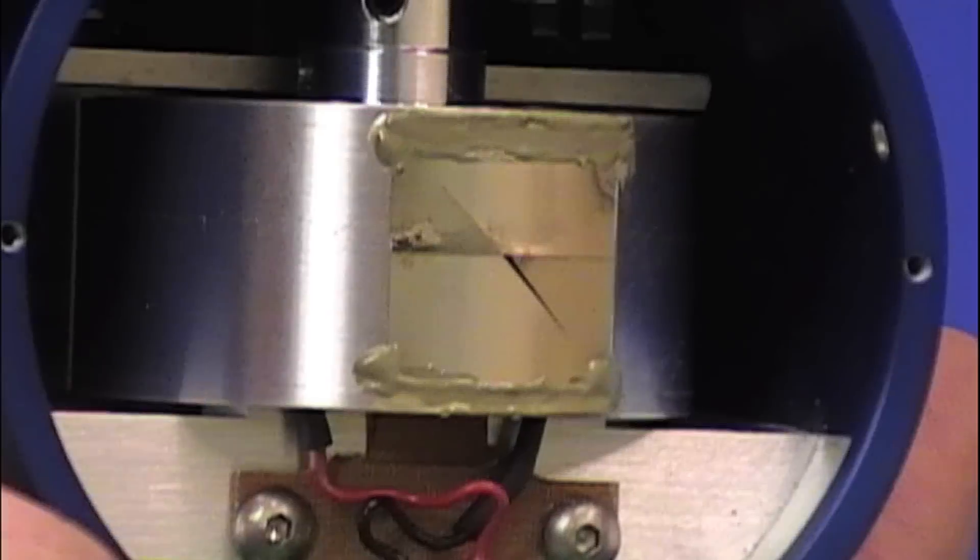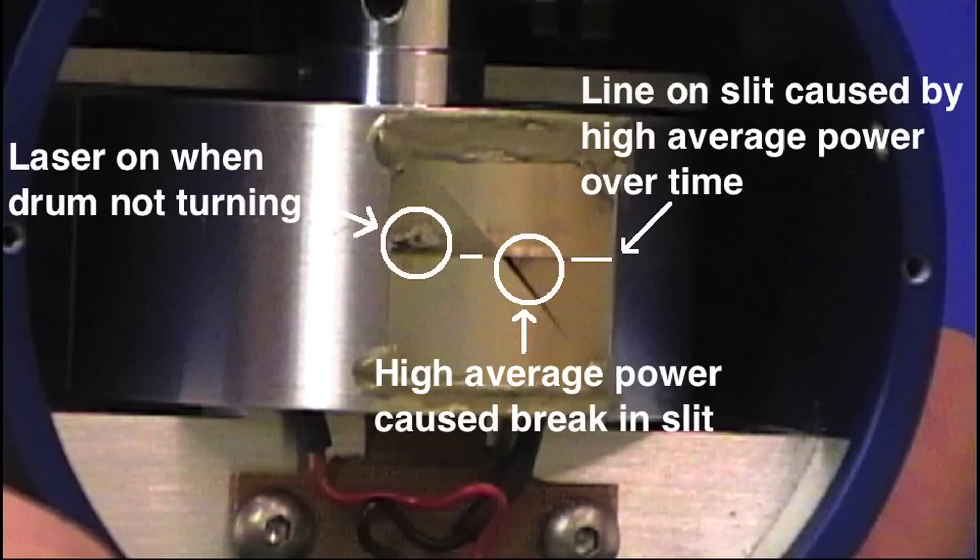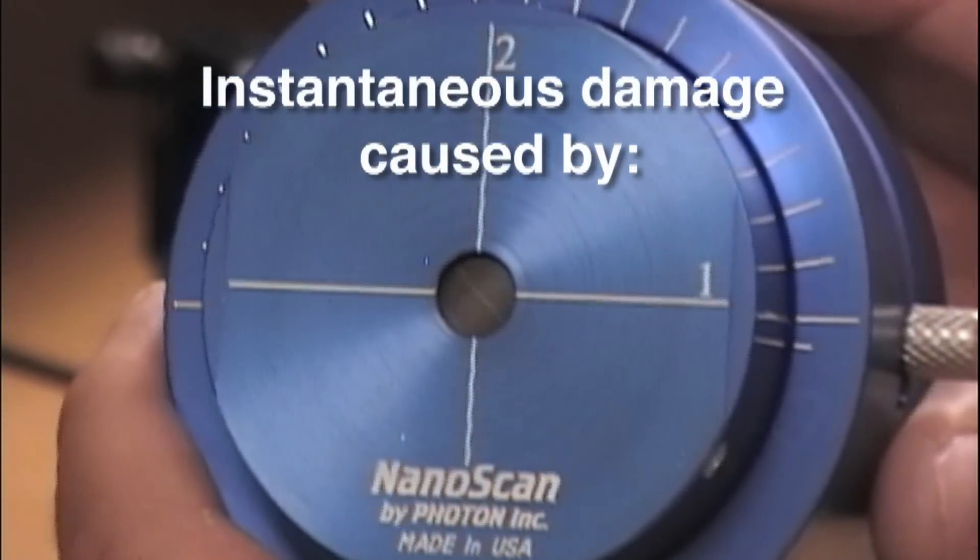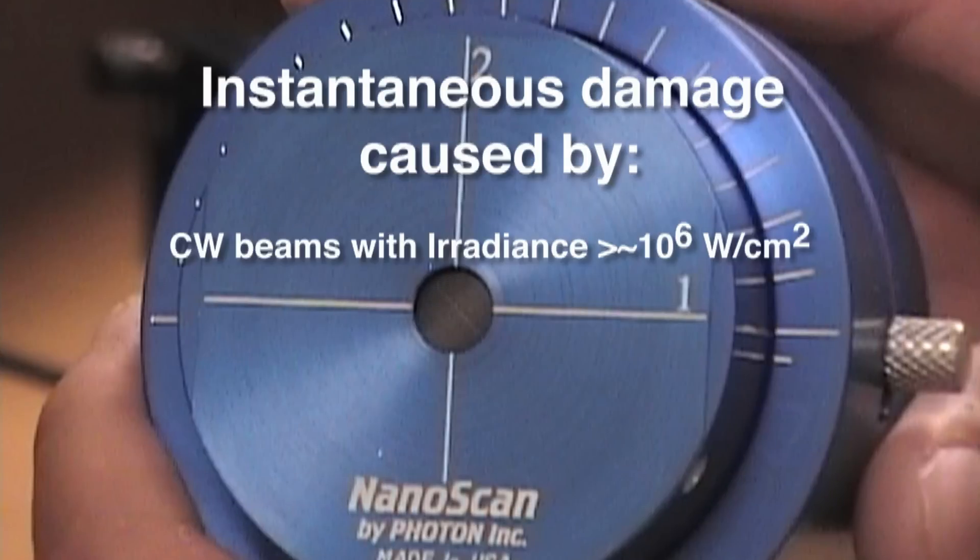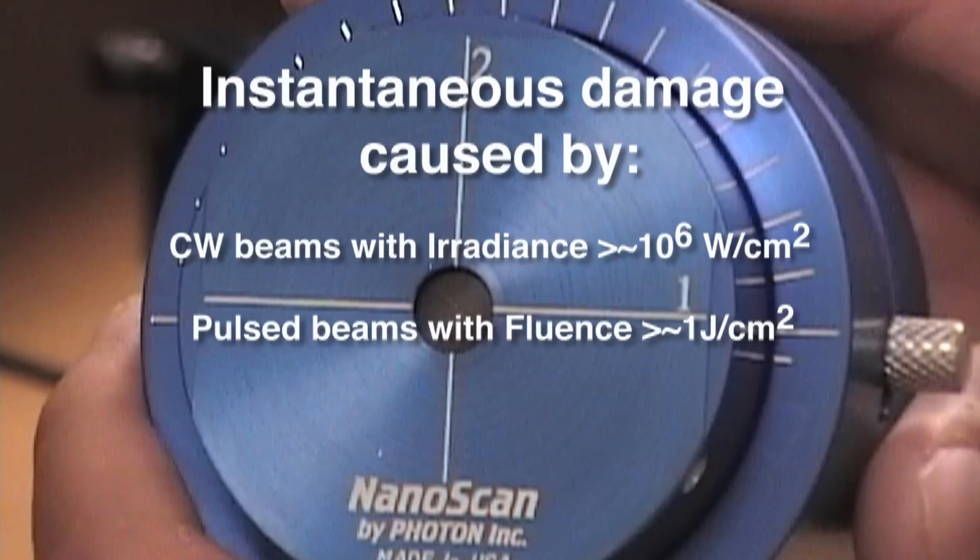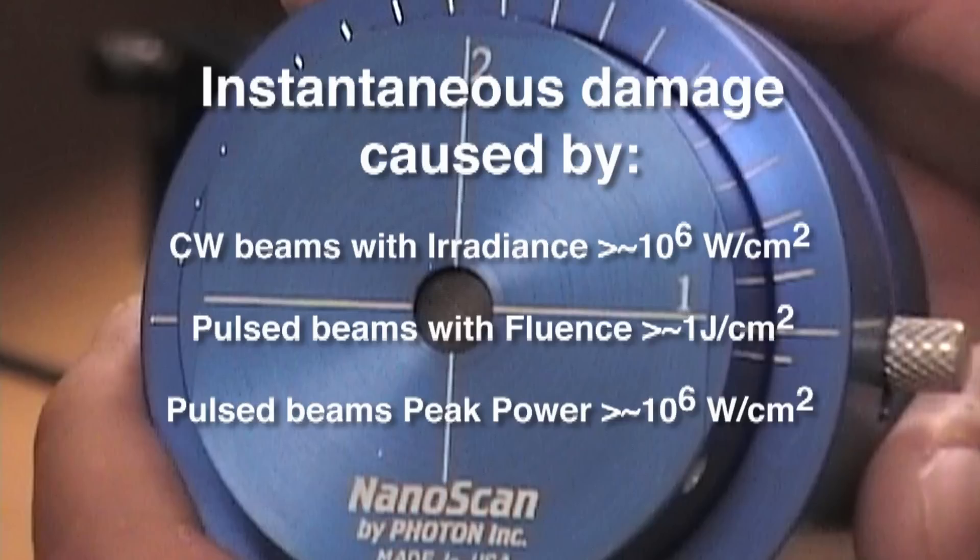It can be damaged by overheating by exposing the scan head to high average power. Instantaneous damage to slits occurs due to exposure to CW beams with irradiance greater than or approximately equal to 1 megawatt per centimeter squared, or from pulsed beams with a fluence of greater than or approximately equal to 1 joule per centimeter squared, or from pulsed beams with peak power greater than 1 megawatt per centimeter squared.